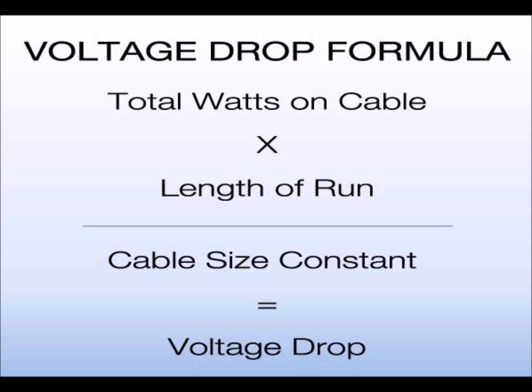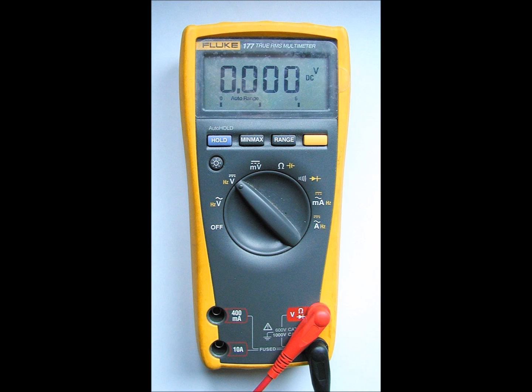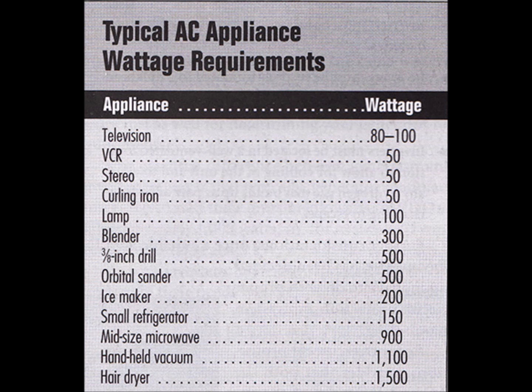Voltage drop is a measure of how much a circuit's voltage fluctuates or drops once a load is applied. Voltage drop can be calculated by comparing a voltage measurement with no load on the circuit to a voltage measurement under full load. Voltage drop can be easily measured with any quality circuit analyzer. This kind of device puts a full load onto the circuit without tripping a breaker or causing any interruption to equipment on the line.